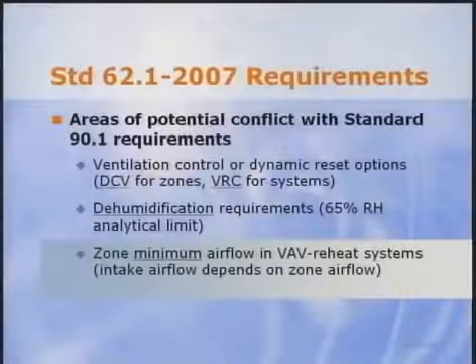So there are a number of ways that a VAV system can comply with this portion of Standard 90.1. Let's bring Dennis back to discuss the requirements of ASHRAE Standard 62.1. Okay, I think we understand what Standard 90.1 does and doesn't allow for VAV systems. The reheat minimum settings can't be too high, otherwise energy is wasted. But Standard 62 requirements also impact primary airflow to each zone.